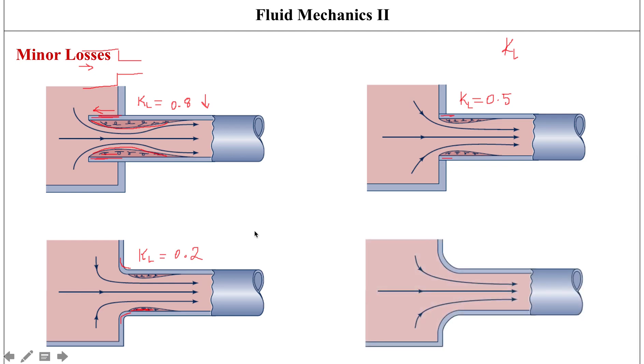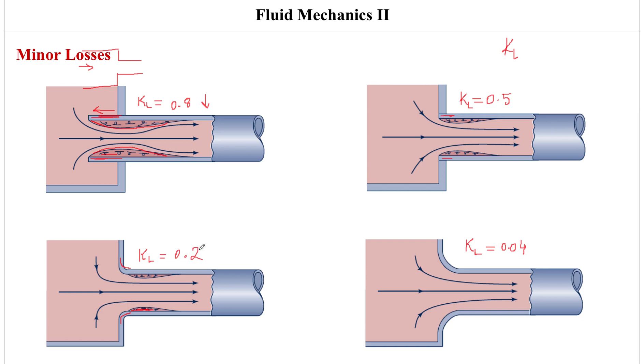We can keep improving this further. The more well-rounded the entrance is, the lower the loss coefficient. A well-rounded entrance can bring KL down to as low as 0.04. However, in practical applications, it's not always just about achieving the lowest loss coefficient — the cost of fabricating these components must also be considered. There has to be a give and take between low head loss and keeping manufacturing costs manageable.